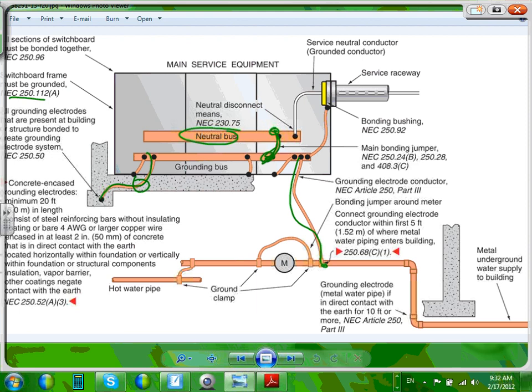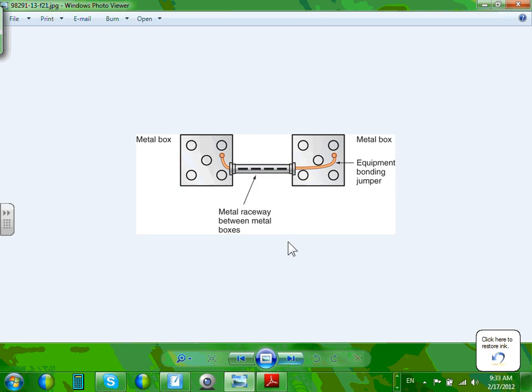And then the service conduit, if it's metallic, they're bringing your service, you also have to bond it. And you can see how they bond the service. They call it equipment bonding jumper, supply side bonding jumper. You have to have a bonding bushing and bond the service conduit. You have to jump around the meter, so if they take the meter, you don't interrupt the continuity of the grounding electrode system. Again, we will come back to these guys and connect them.